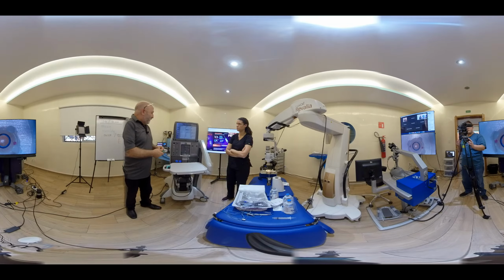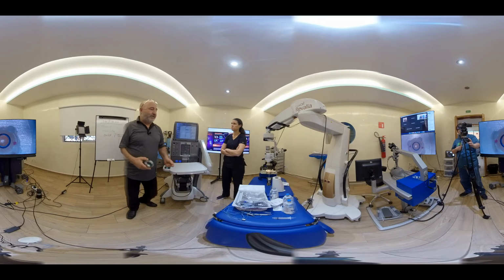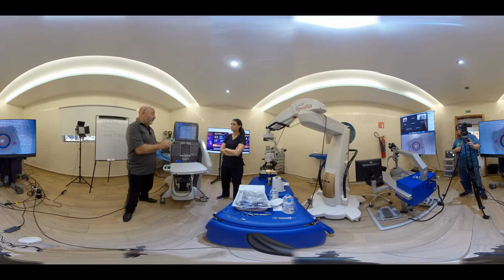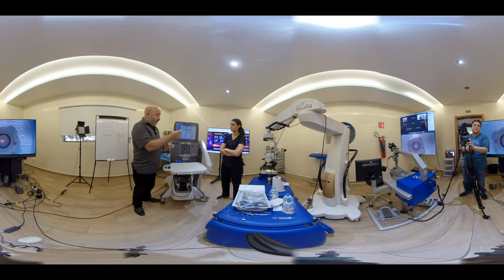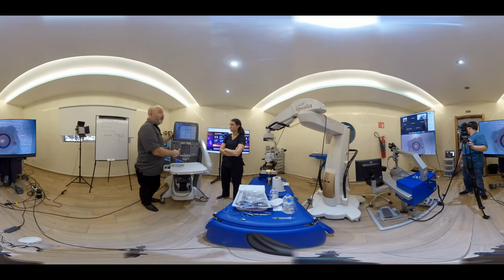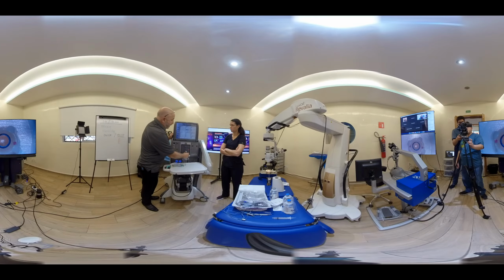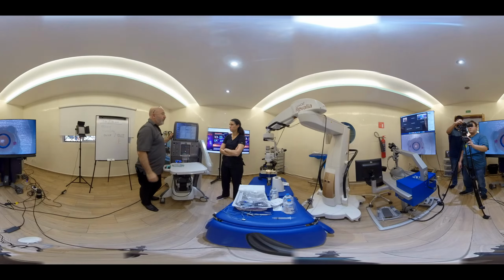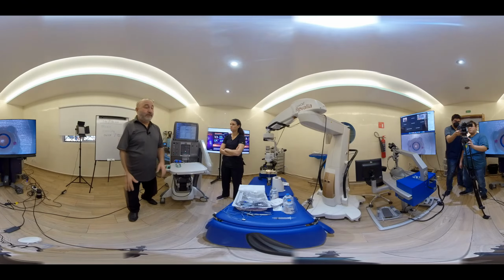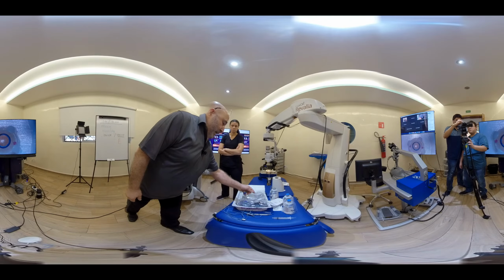Now, those of you that know me know that I'm obsessive compulsive and I do things a certain way, but I do things for reasons. I always like to put the connections on the cassette while the cassette is in the machine. And the reason is I want to use leverage, and I do put a lot of leverage on this. It needs to be at least at 2 o'clock, the little indicator tabs. If it's not, I've seen air being sucked into the tubing that goes into the lines, and that's not good, apparently.